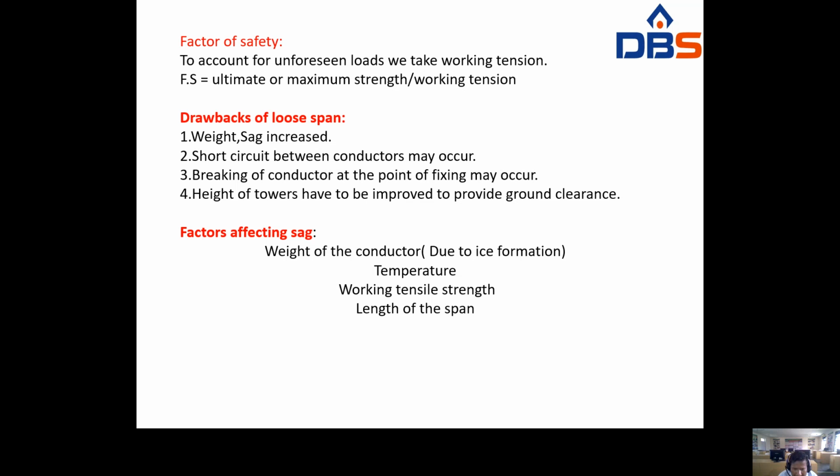So the factors affecting the sag are: S is equal to omega L square by 8T, where omega is the weight of the conductor, T is the tension, and L is the length. Apart from these three parameters, the sag is also affected by temperature.